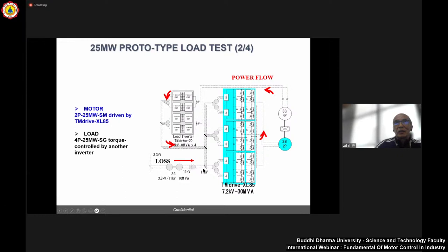So this one, we call it a power run back testing system, where we supply the power to the motor driving unit here, and this one controls the motor. And then this one connects to the generator. Generator power goes back to the original power supply line using this drive. So this is for regenerating, and this is for motoring, for this synchronous motor.